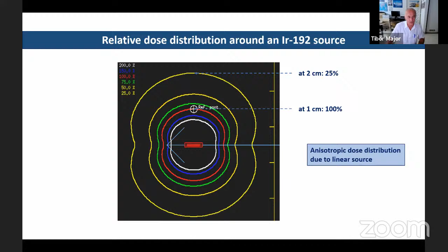A few words about quality assurance. Imaging is always used before brachytherapy treatments. With imaging, we can reconstruct the source positions in 3-dimensionally. With this phantom, the accuracy of the imaging and the reconstruction was checked. There are many small metal spheres in this phantom, and their coordinates had to be determined with imaging and reconstruction.